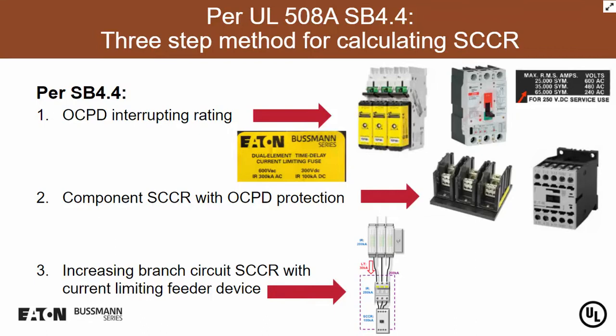Then we move into step 2, and step 2 is looking at the components. On the right of the slide, you're going to see the power distribution block and the contactor. In general, a contactor is rated for 5 kA, and in general, a power distribution block is rated 10 kA. Well, we need panels and machines to be higher rated than that. So step 2 is looking at the component SCCR along with the associated overcurrent protective device. So for instance, if we have a contactor with a breaker, let's say the combination rating could be 35,000 amps. So now that brings that contactor rating from 5,000 amps up to 35,000 amps.